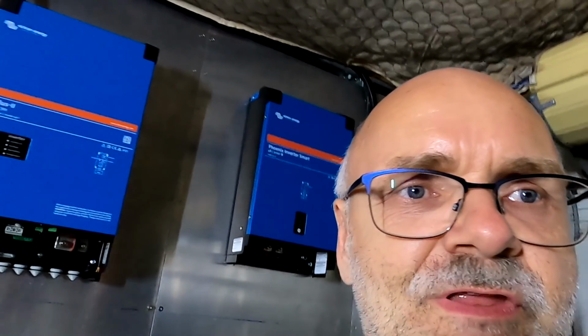I should have done more research about these circuit breakers. I thought they were already available up to 125 amps or so, but the DC breakers from Noark only go up to 63 amps, and everything 100 amps and above uses these industrial MCCBs we've used here. But obviously we cannot mount them on the DIN rail at the front anymore.